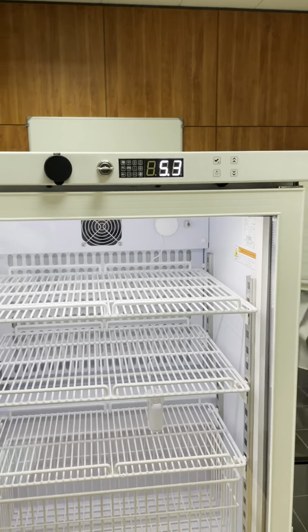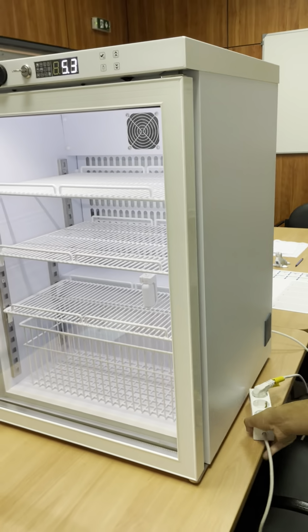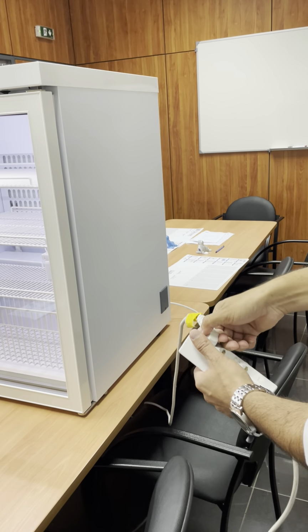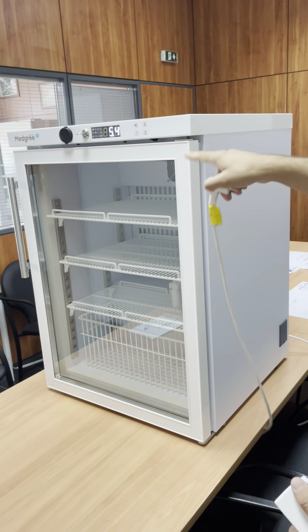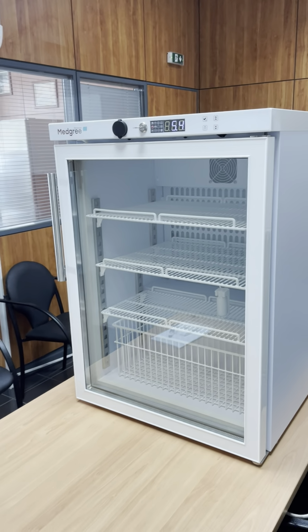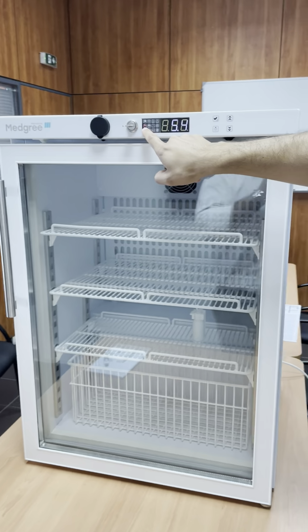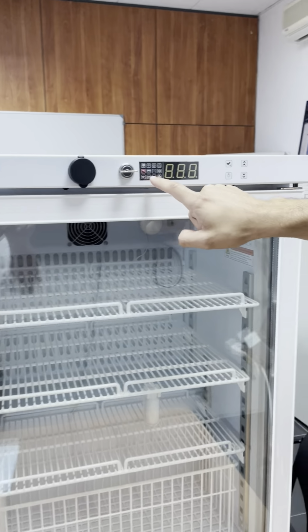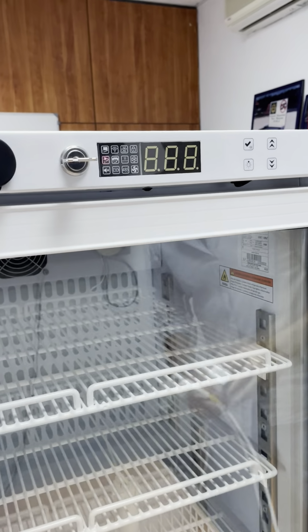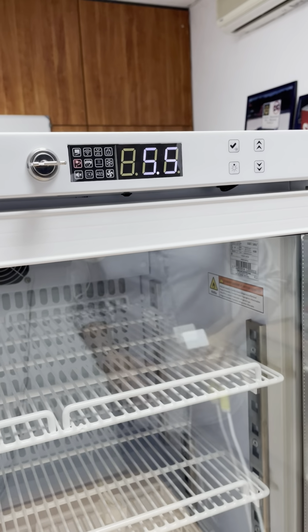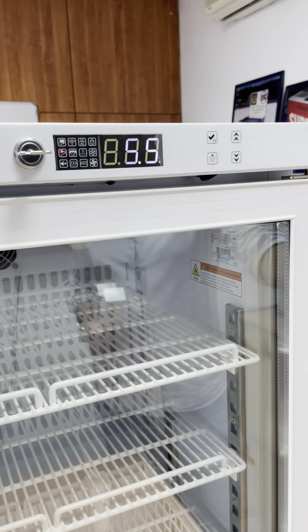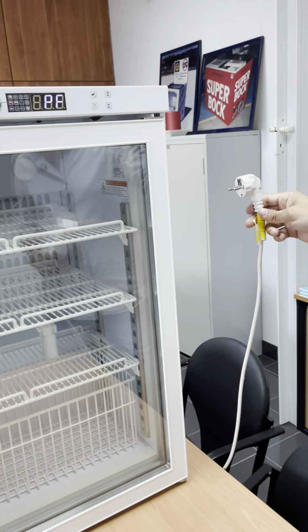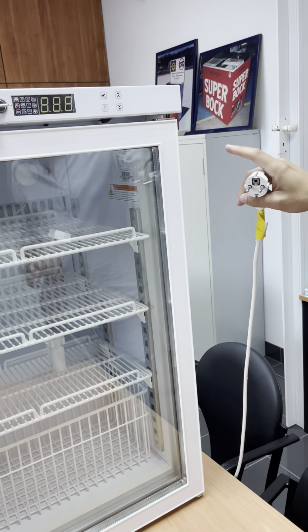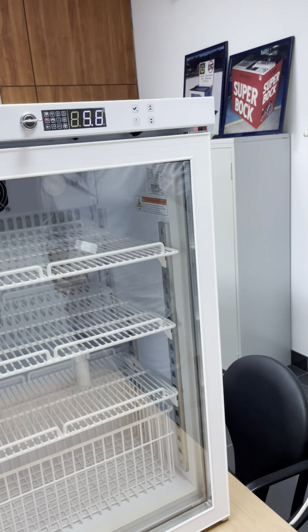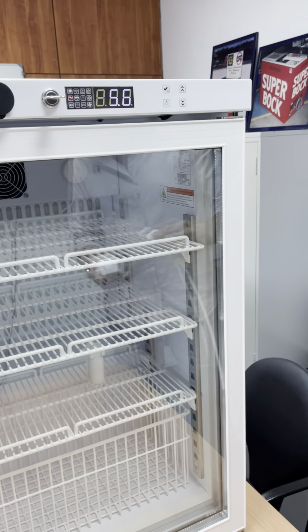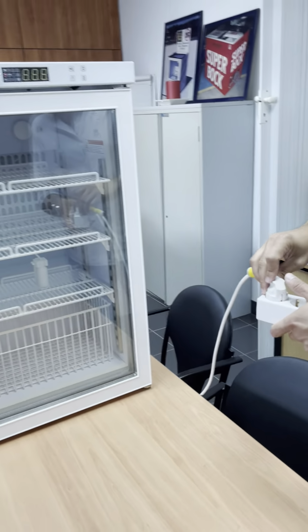So to do this, I will just show you. So I will disconnect it. The equipment is not working anymore. Power failure appears, and you have a PF. So this is the alarm. You don't have a power connection, but the controller is still working and recording everything in the equipment.